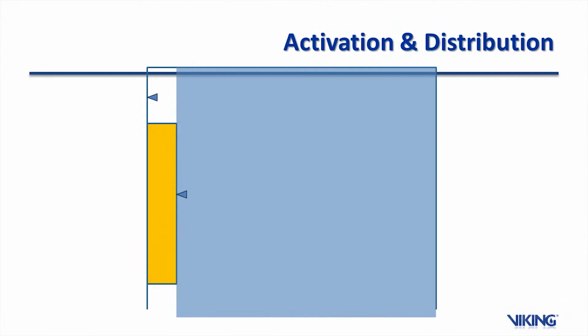Okay, this is not a big space, maybe 15 by 2 feet. And sure enough, there was a sprinkler there. Now, how much of the floor area is this sprinkler actually protecting? Hold on. That right there. Everything it reaches. Well, yeah, but this has already got everything else. This thing really is only going to protect this.